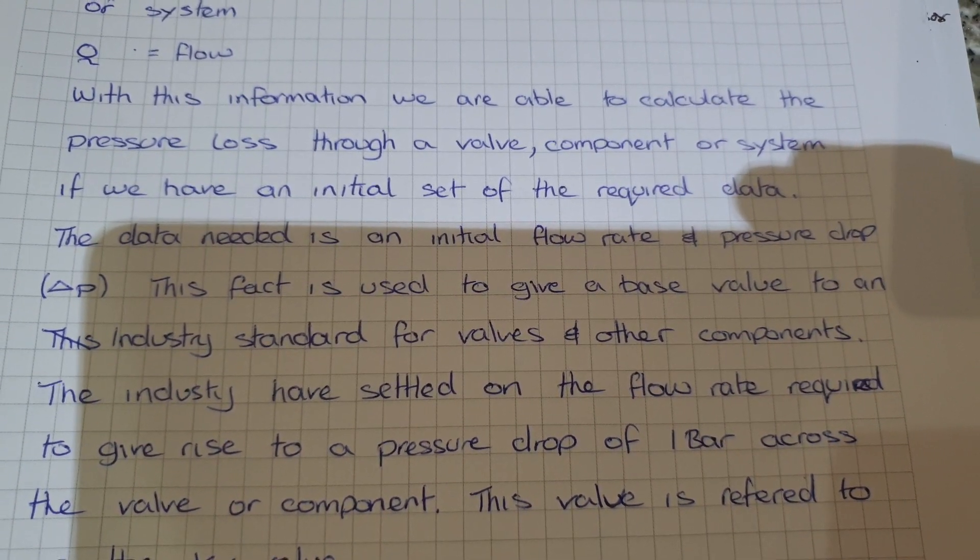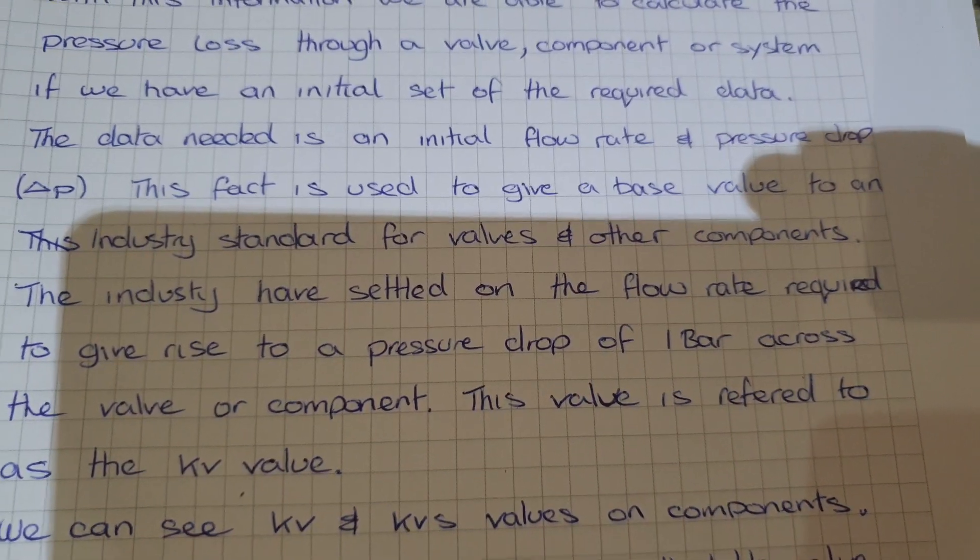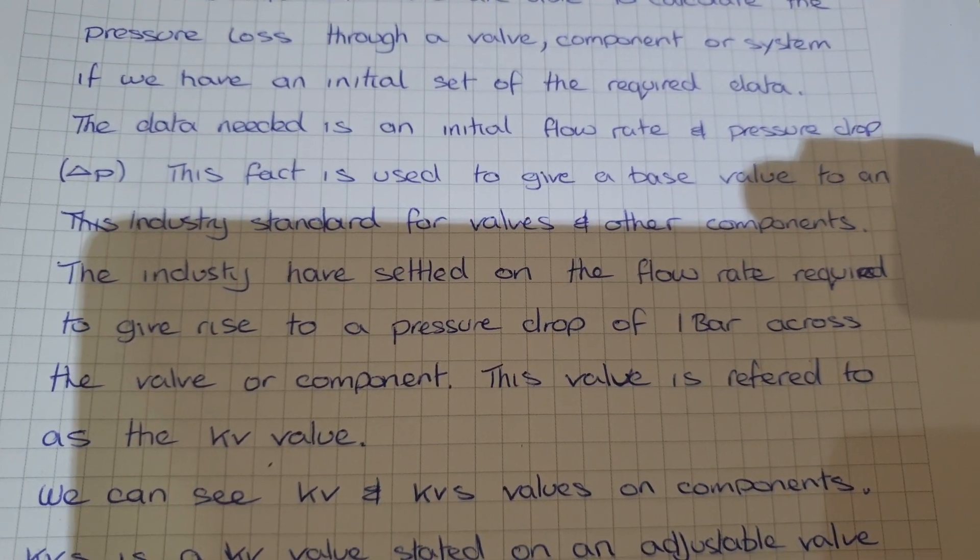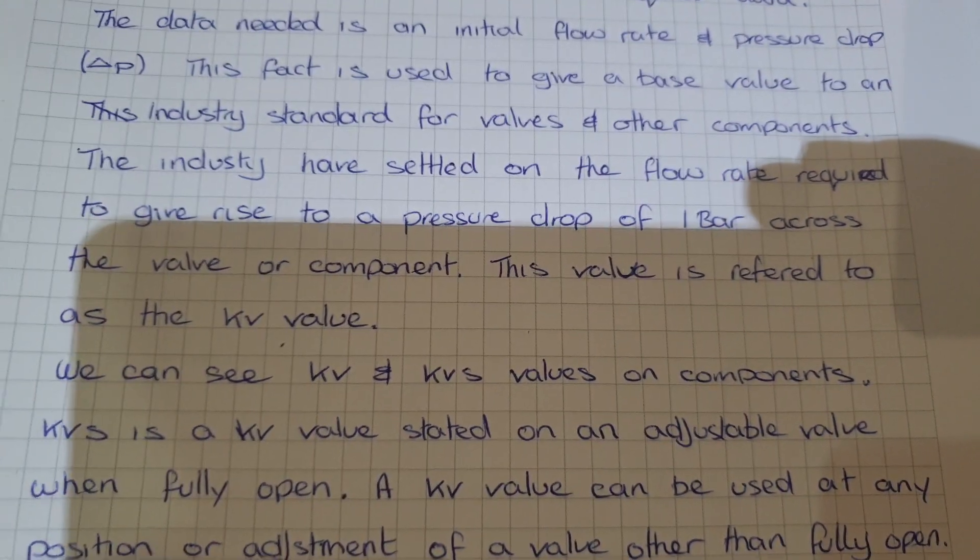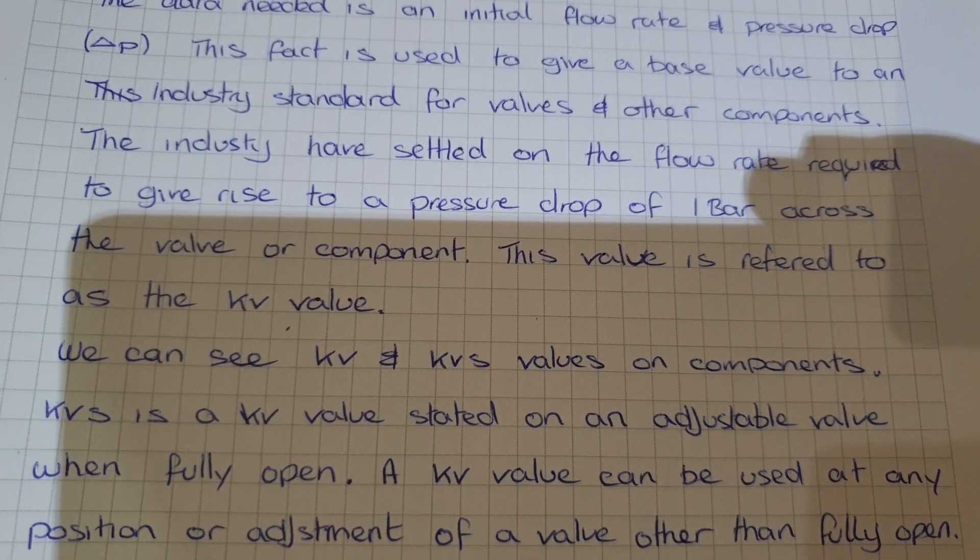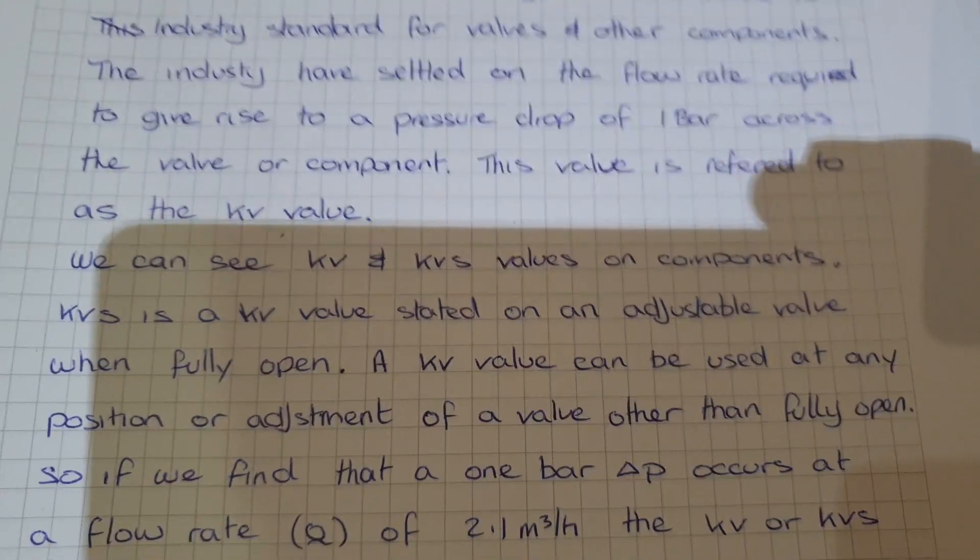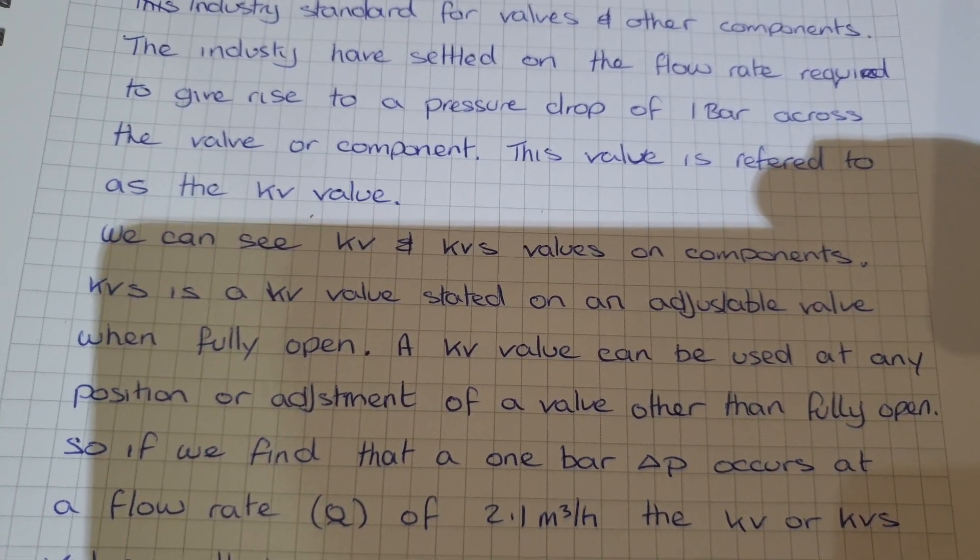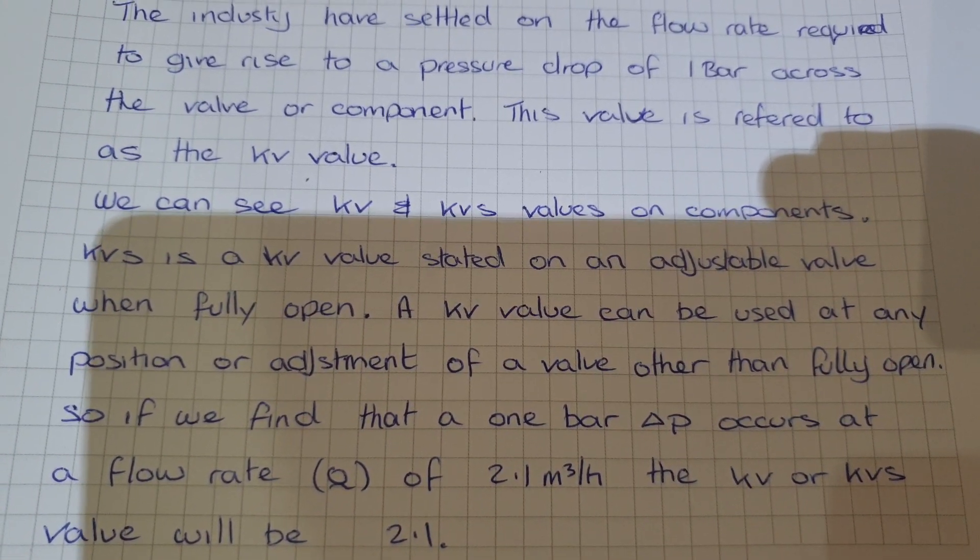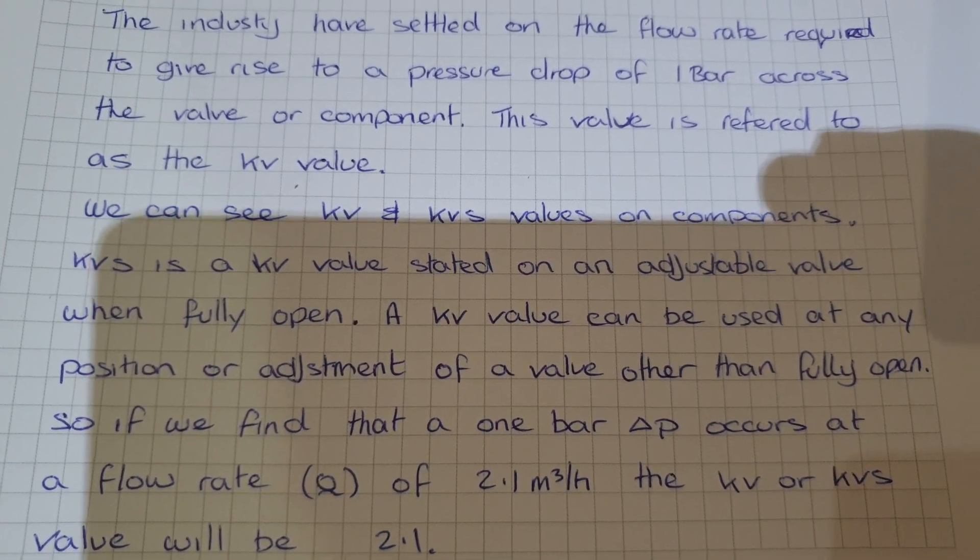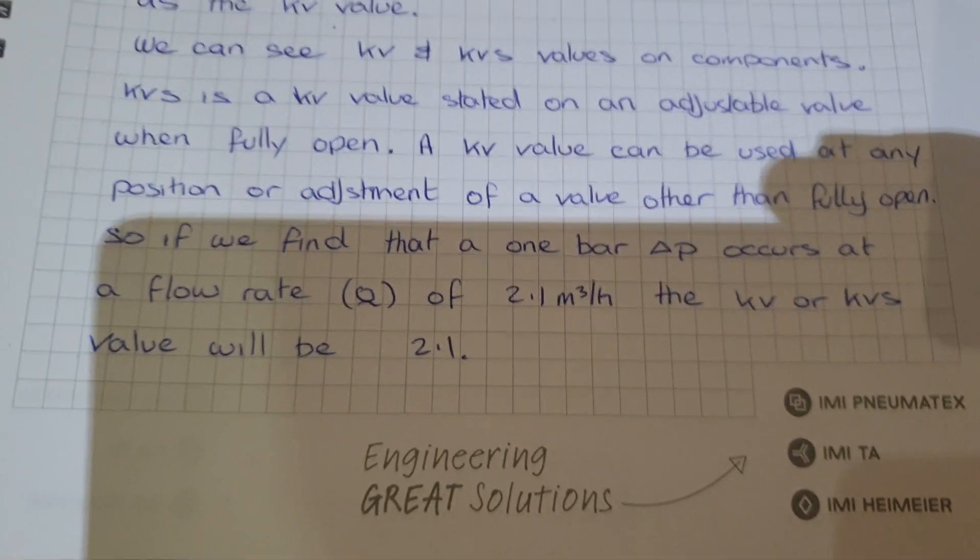The data needed is initial flow rate and pressure drop (delta P). This fact is used to give a base value to an industry standard of valves and other components. The industry have settled on the flow rate required to give rise to a pressure drop of one bar across the valve or component. This value is referred to as a KV value.